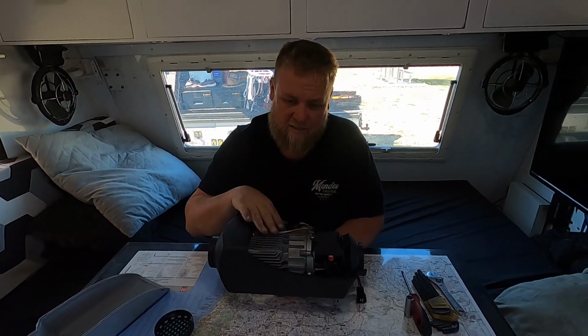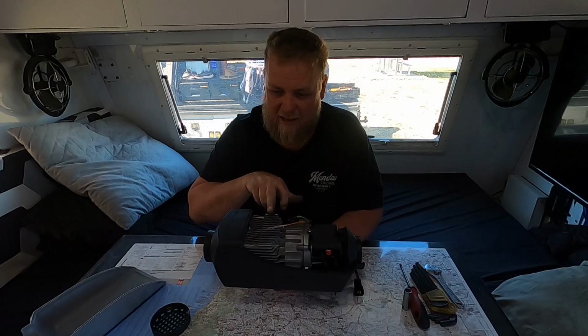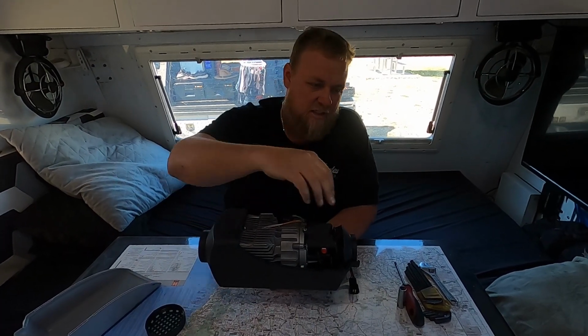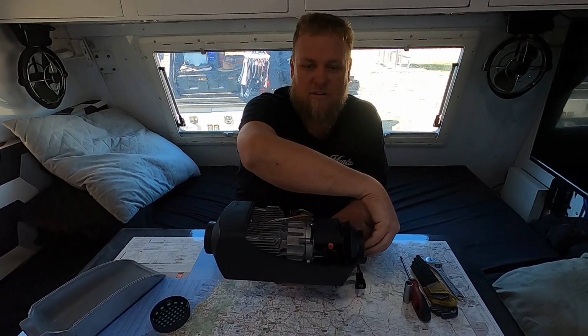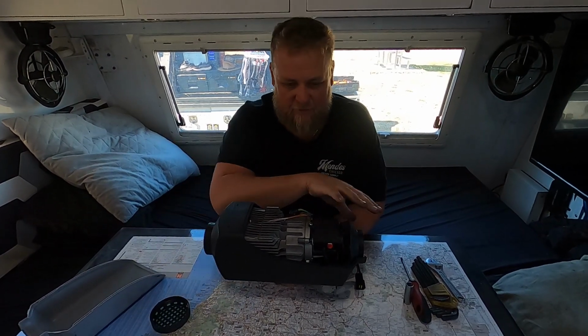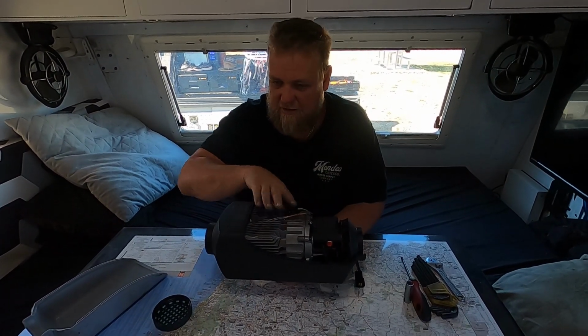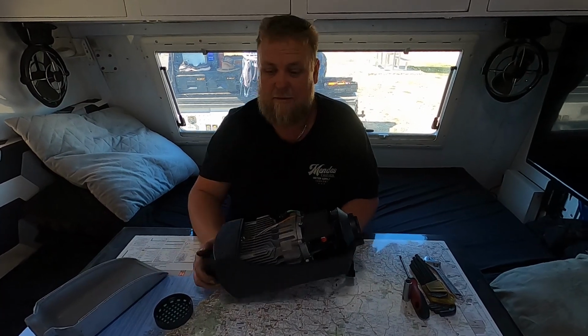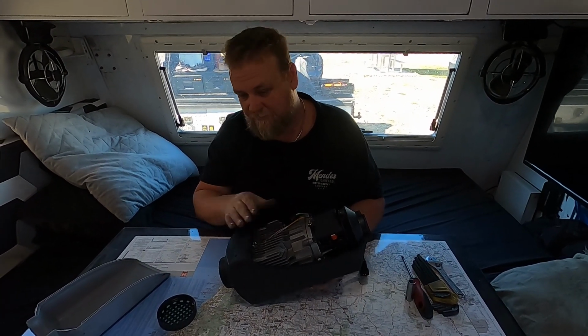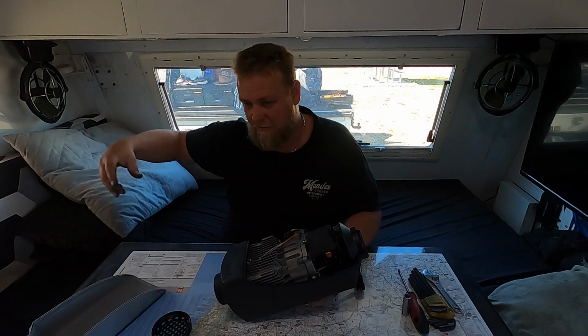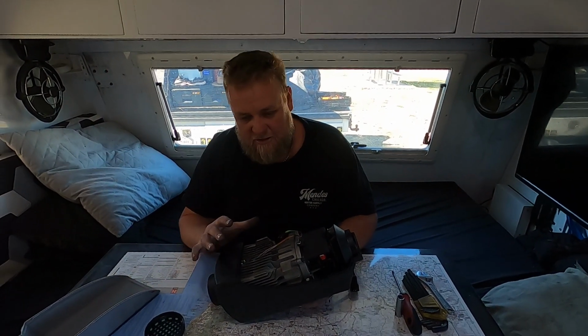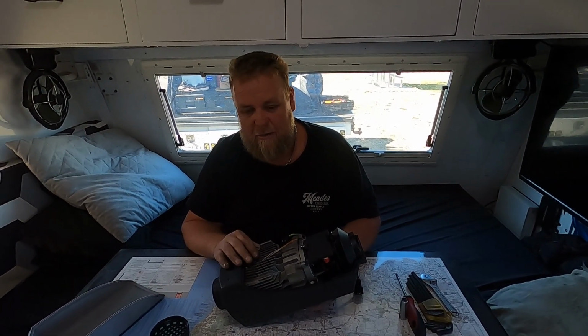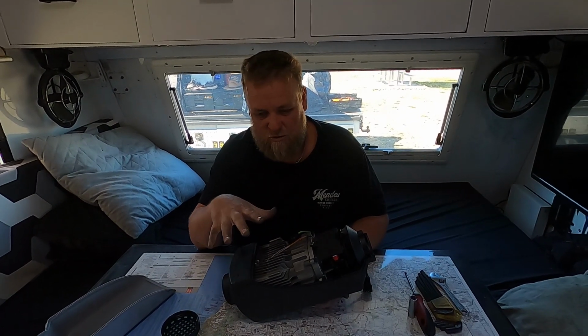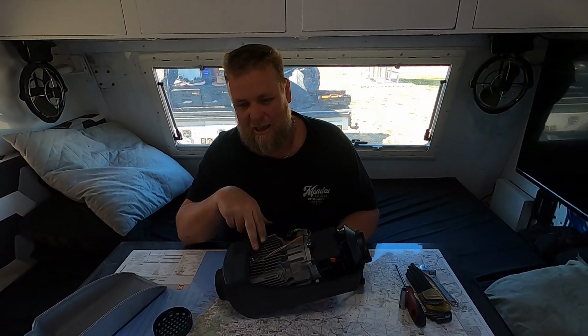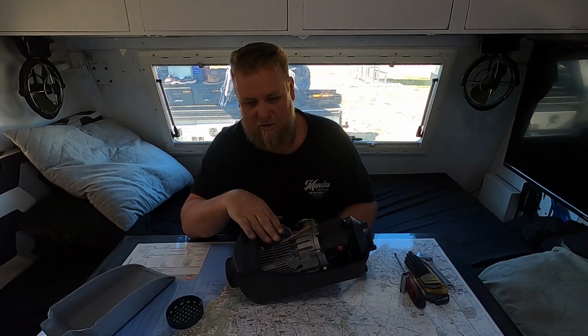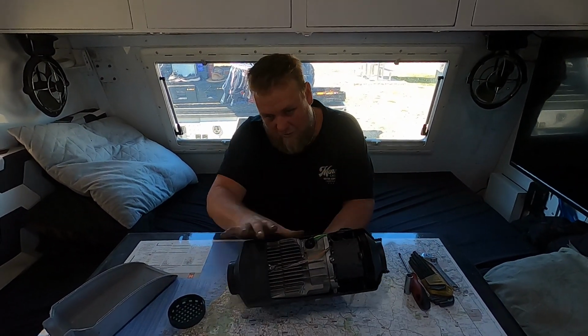The actual heating is from the external of this heat exchanger. You have air sucking in from this side, which in our case is under our dinette. The air blows past all of this, past your heat exchanger, which would be glowing hot, blowing hot air out this side through your duct, through your van. So your actual hot air is not coming from any heating source directly - technically it's just coming from this hot aluminium. That's the only way you're getting your hot air, from the air blowing over this unit.